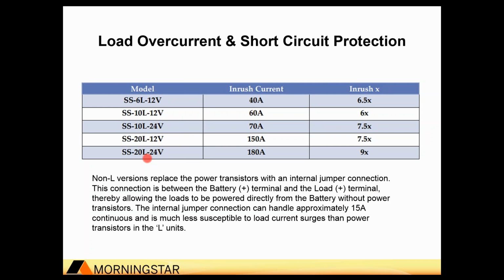As you can see on the 20 amp model, you have almost up to 180 amps of inrush that it can accept for a short duration, a short burst, to let you operate loads that might have those inductive inrushes without an issue and still have the benefit of LVD.